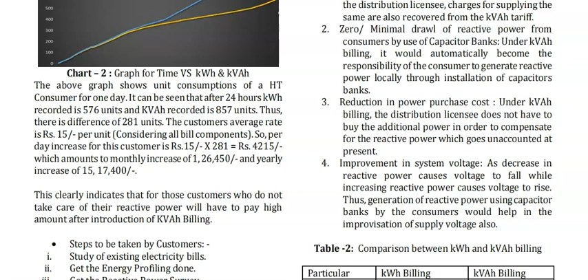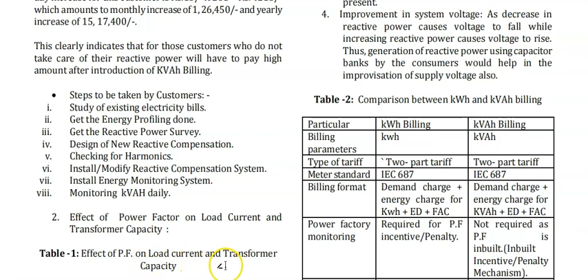Step by step for the consumer: study the existing electric bills, get an energy profile done, get the reactive power survey, design the new reactive compensation, check for harmonics, install or modify the reactive compensation system, install an energy monitoring system and monitor kVAh daily. The second point is the effect of power factor on load current and transformer capacity. Table 1 shows this effect. Now we will see Table 1.